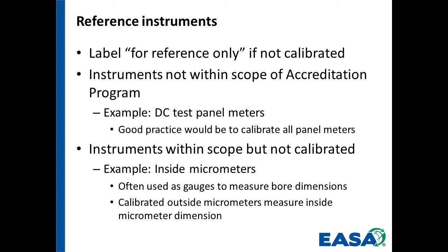And if you have an item that you're using for testing, for example the DC test panel, or your DC voltmeter, DC ammeter: accredited repairs at this time, the scope of it, is 3-phase squirrel cage induction motors. So a DC motor, you can't put an accredited repair label on it because it's not within the scope of the program. If you test a DC motor, to make it clear, especially to an external auditor, that you don't use that panel for testing accredited repairs, you can mark the panel for reference only. I would encourage you to get it calibrated anyway, just as good practice. If you've got known calibrated meters for your AC accredited repairs, wouldn't it be good to have them for your DC too, to give your own firm a higher level of confidence that the values you're measuring are correct, that they're accurate.